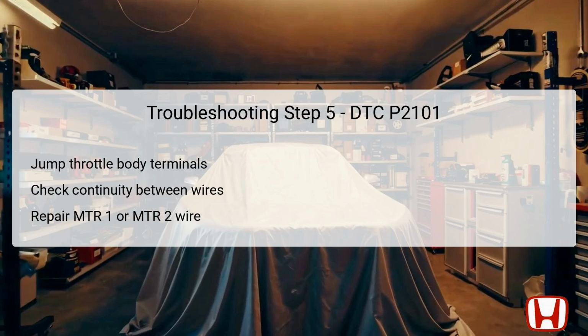Measure continuity between the specified test points for both MTR1 and MTR2. If continuity is confirmed, the wiring for both motors is fine. If there is no continuity, it means there is an issue with either the MTR1 wire or MTR2 wire extending between the throttle body and the PCM that must be repaired to restore functionality.